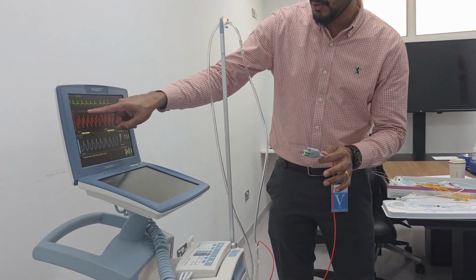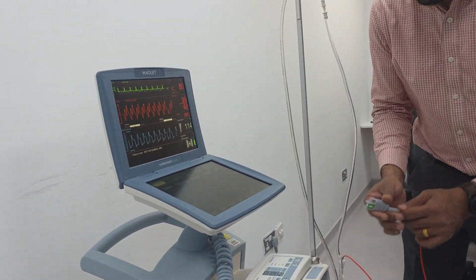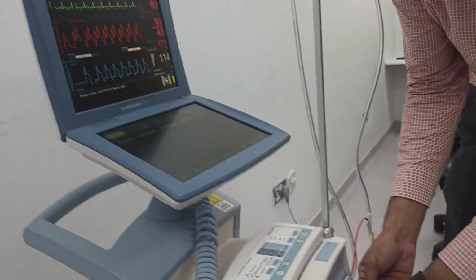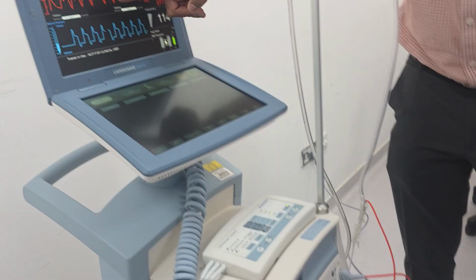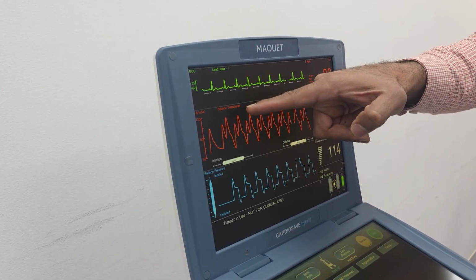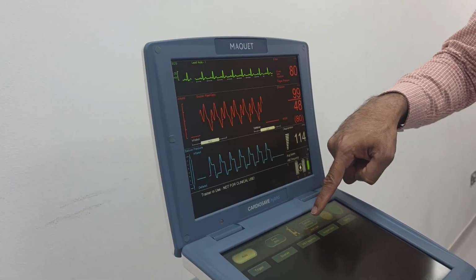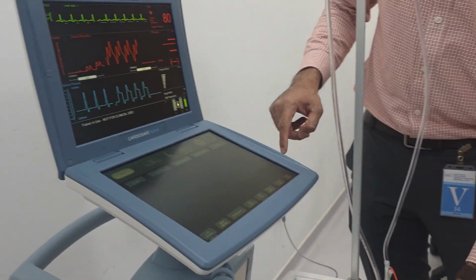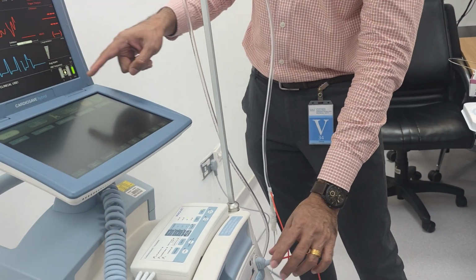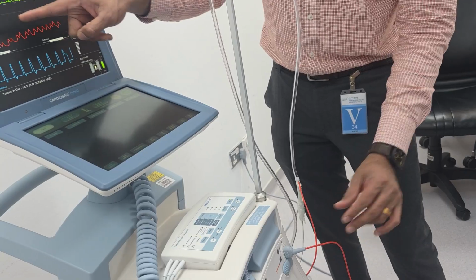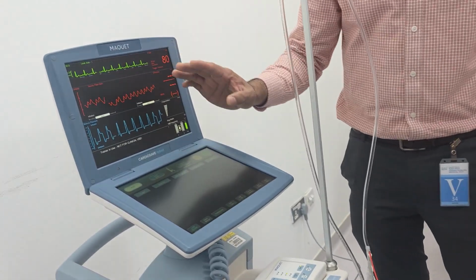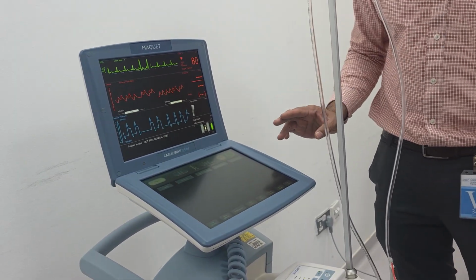And see the difference again. Now it's showing transducer. When I connect this one, this will change. And here also you can see which is the source, whether it's fiber optic. That's important. Sometimes it gives fiber sensor issues, so make sure that it's fiber optic. You connect it, it should change. That's how you can recognize whether the connection is okay or not.